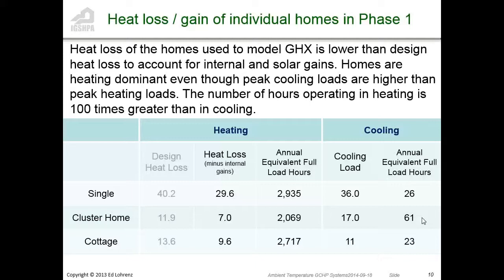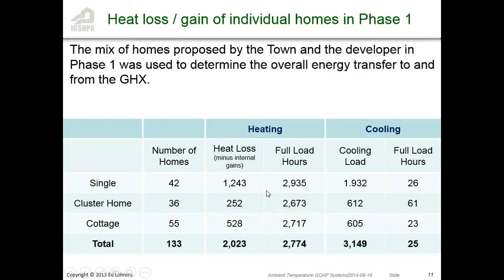So basically we looked at different types of buildings and typical house sizes they were looking at: heat loss, annual equivalent full load hours, cooling load, full load hours, and did our best guess at what those were going to be. Then looked at how many of each they were going to build. In the first phase, they were going to build 133 homes, looked at what the total heating and cooling loads were, and designed enough ground loop based on that.